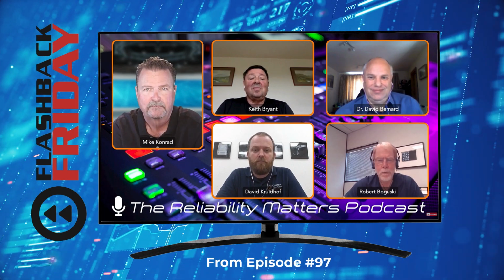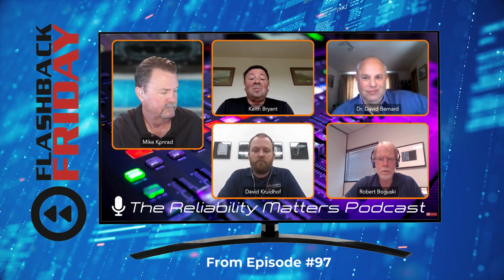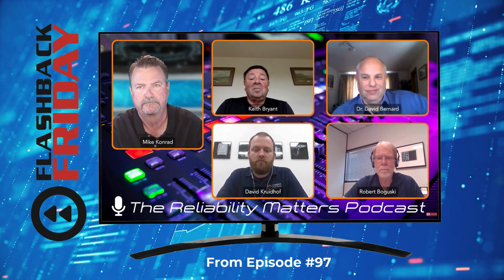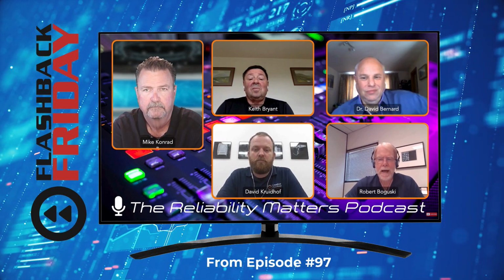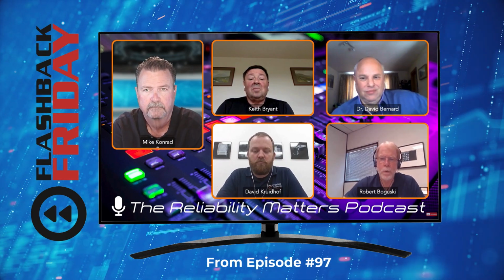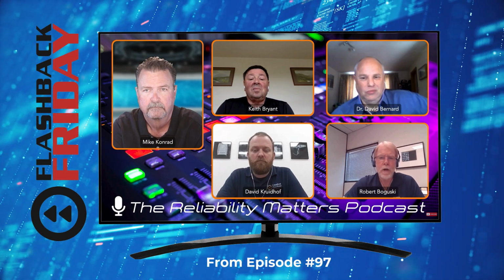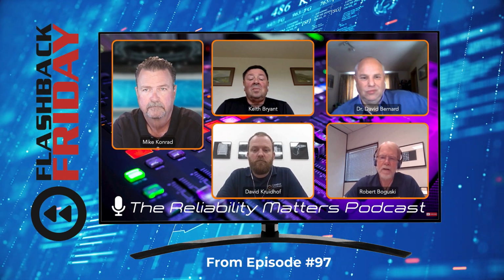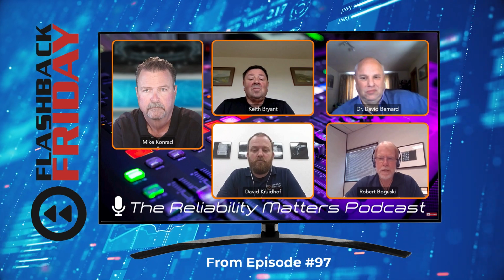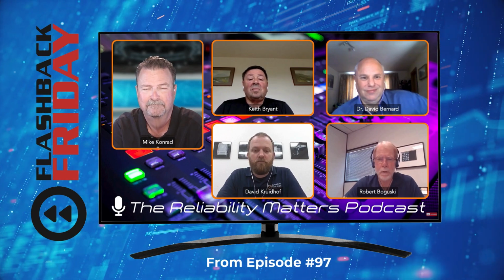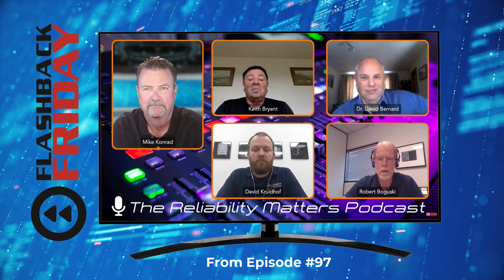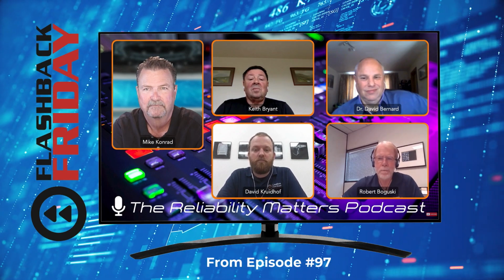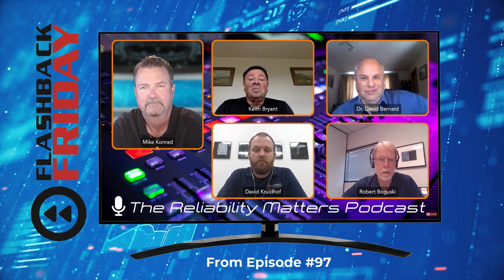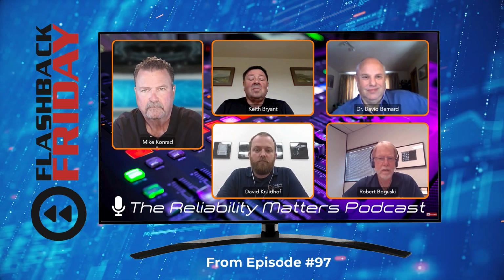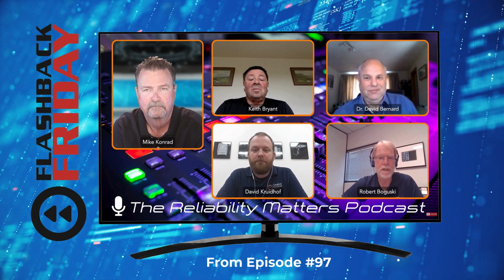To Dr. David's point earlier, CT is expensive because it's time consuming. True CT, some of our more complex applications on things like additive manufactured parts or castings or things of that nature, we often put the part in the machine at 5 p.m. or 6 p.m., set it up, hit start and go home. And we come in the morning 8 to 10 hours later, and we have several terabytes worth of images ready for post-processing. That's what it takes. And it's available for those who wish to pay for it, but it is an expensive process because of that.